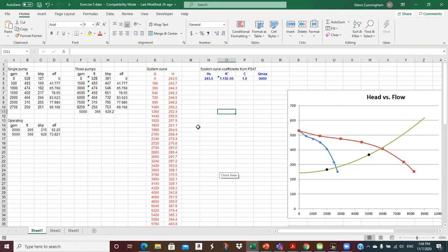Okay, so this is what a file looks like that gets exported from PSAT. You get coefficients up here. It will plot out your system curve for you. I mean, you can do this for yourself easily. And now to this has been added the single pump curve, GPM, feet of head. So we got the manufacturer pump curve, and we just translated these 6 or 7 points.